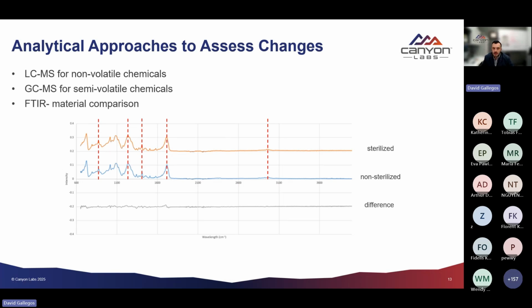Some of the analytical approaches we can use to assess changes in packaging post-radiation: LCMS, which is liquid chromatography mass spectrometry, is an analysis for non-volatile chemicals. We also do GCMS, or gas chromatography mass spectrometry, for semi-volatile chemicals. We want to do both tests to cover the complete array of possible chemicals that are generated, so we don't miss anything. We can also perform FTIR, and this is a graphic that I show here. We use this to compare sterilized and non-sterilized materials, so we can see any chemical changes that may pop up after sterilization. It's an easy way to visualize if there are new functional groups after sterilization. Any degradation, we'll see it here.